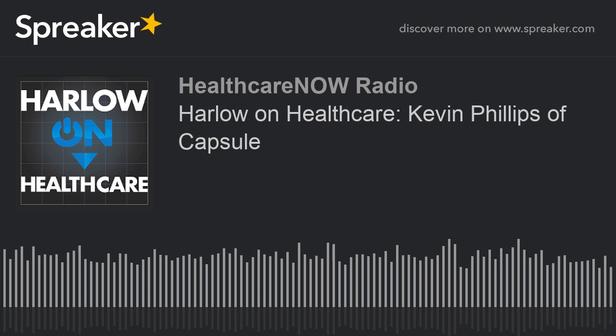So there was a big wave to push to connect these monitors and all other devices, so that alarms could be heard, annunciated remotely. And then from that, we saw a wave of alarm fatigue because there are hundreds of alarms coming off each of these devices in the patient room. And now propagating those out to the assigned clinician led to another scenario, where 85 to 95% of those alarms are not clinically actionable. So phase 2 was certainly national patient safety goals, where hospitals had to have clear guidelines for how they standardize their alarms and ensure a safe and effective use of those in practice.